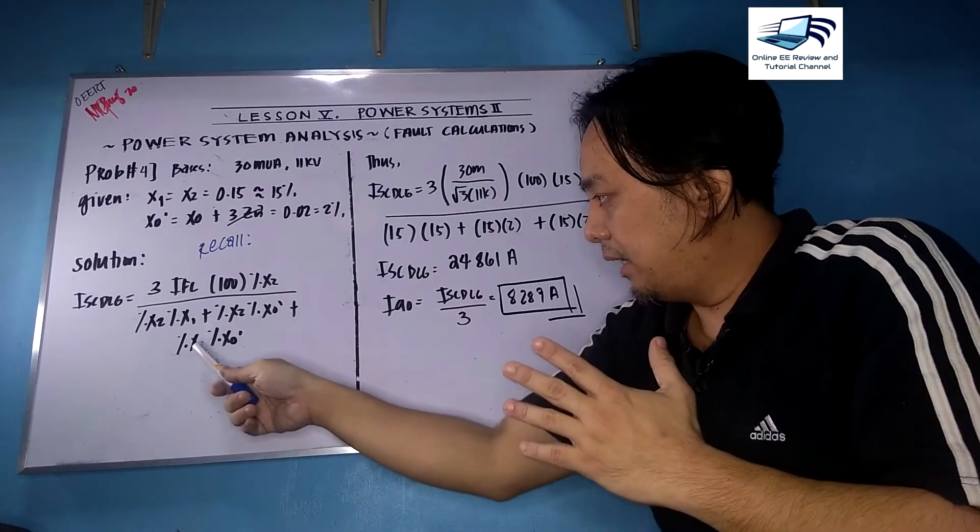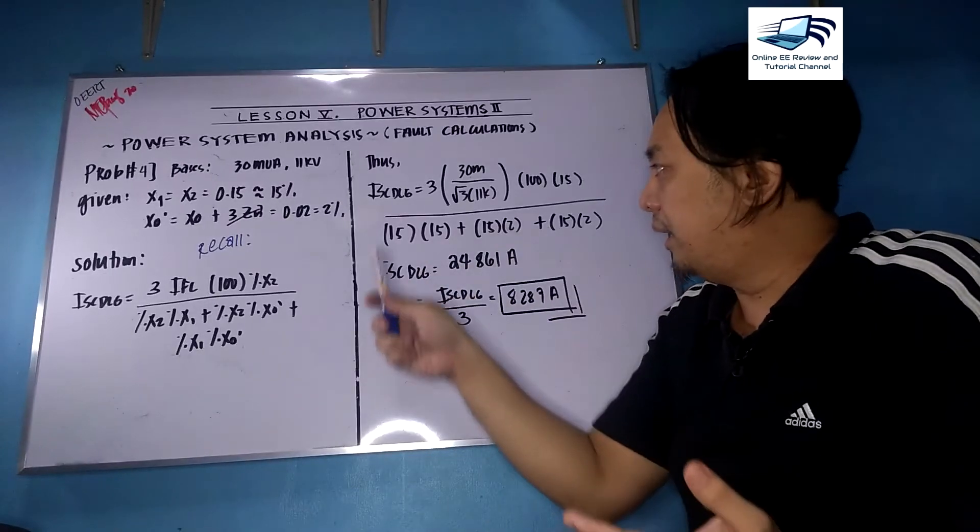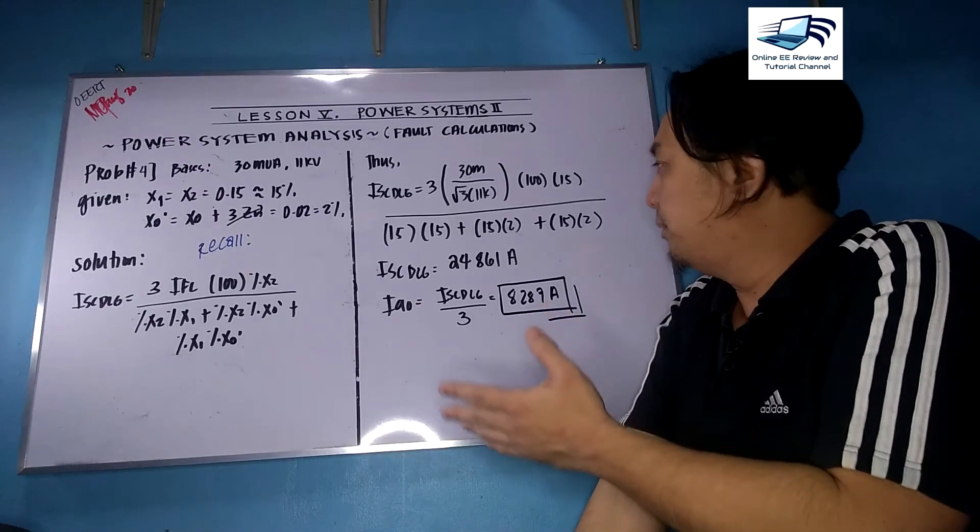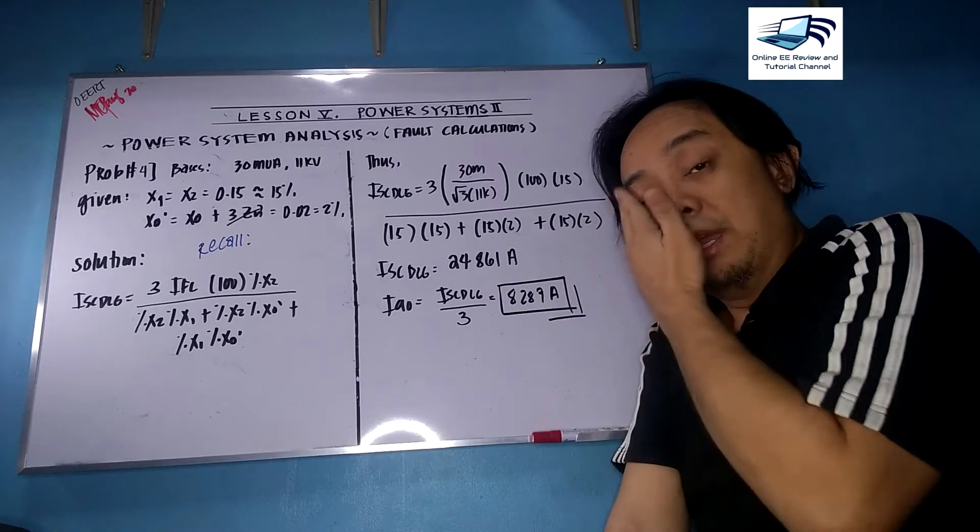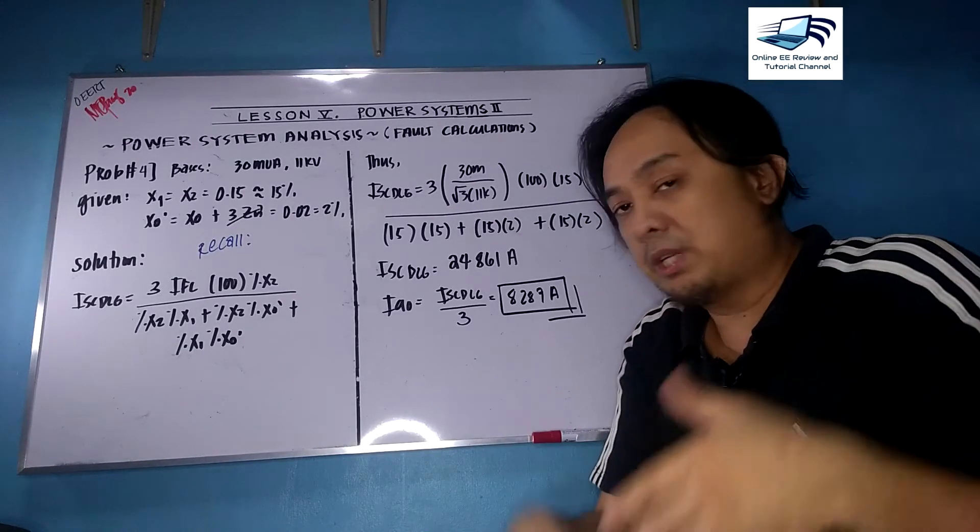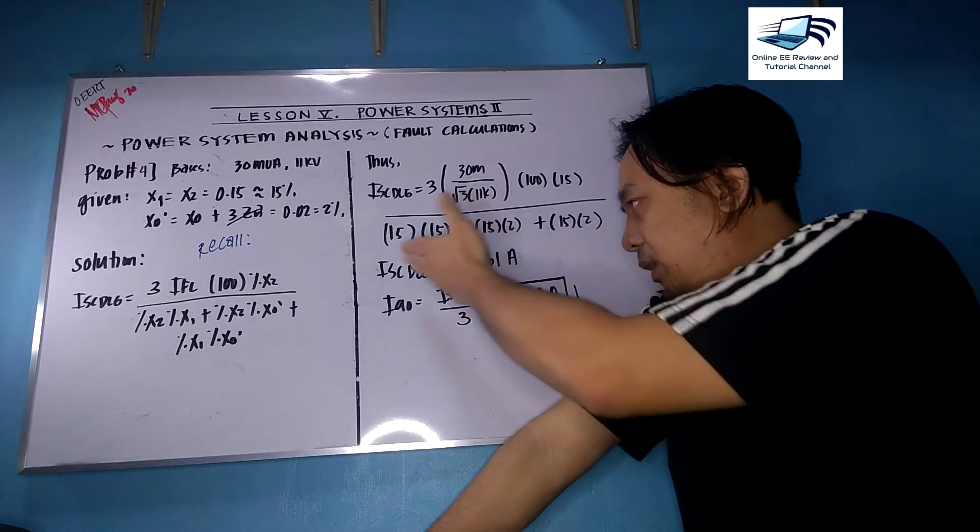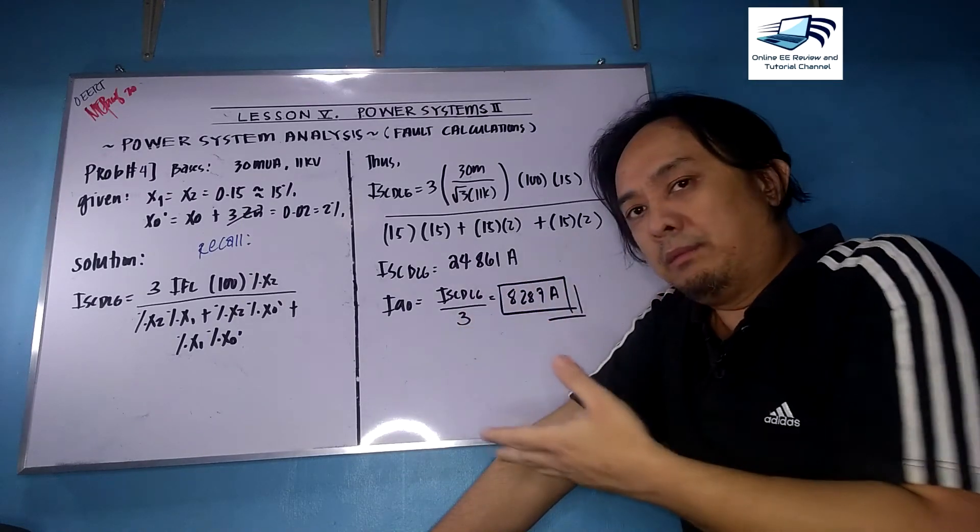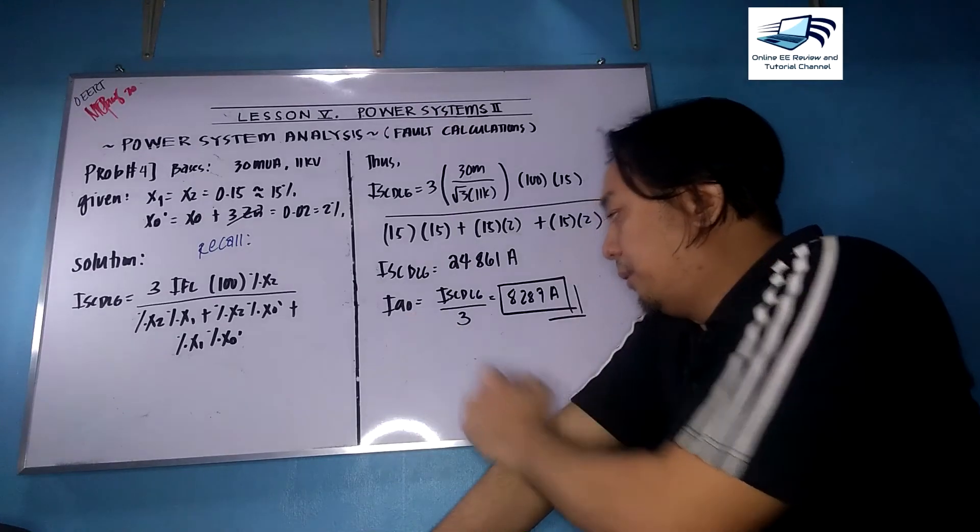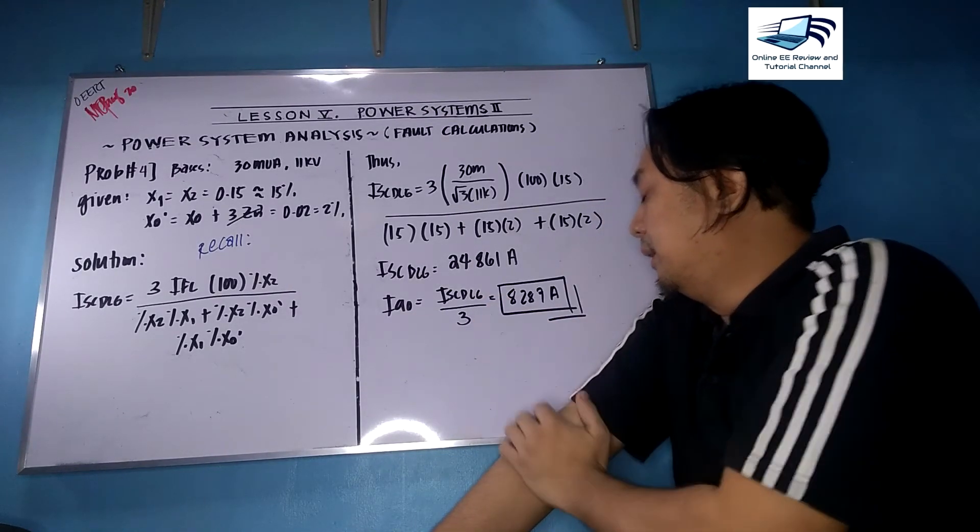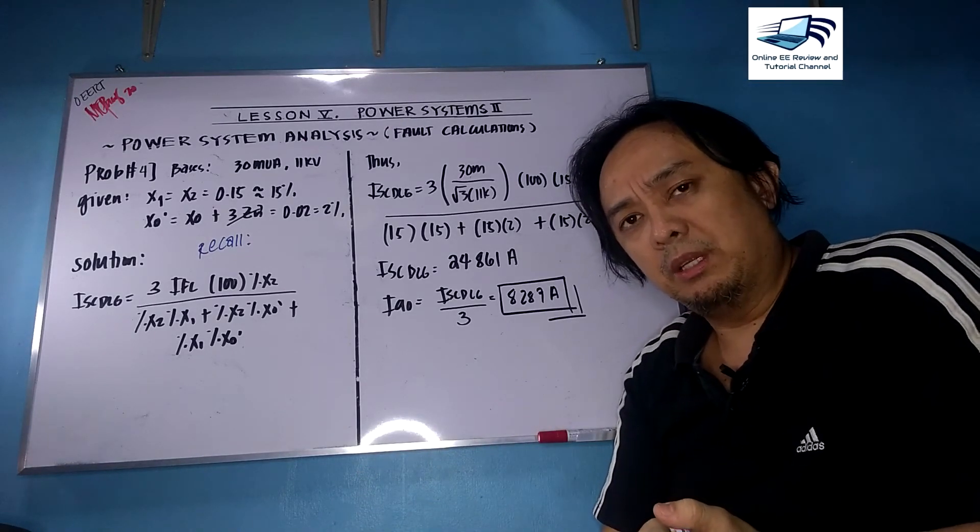X0 prime is simply equal to X0 here because there's no impedance to neutral. Substitute all the values for ISC DLG: you have 3 times 30 million over square root 3 times 11k times 100 times 15, then 15 times 15 plus 15 times 2 plus 15 times 2. The answer is 24,861, but this is not the final answer. It's not always the short circuit current that is required, but you need to get the components of the currents: can be IA, IB, IC, or even the terminal voltages. In this case, IA0 equals ISC DLG divided by three, and thus the answer is 8287 amperes. That will wrap up our discussion on unsymmetrical faults.